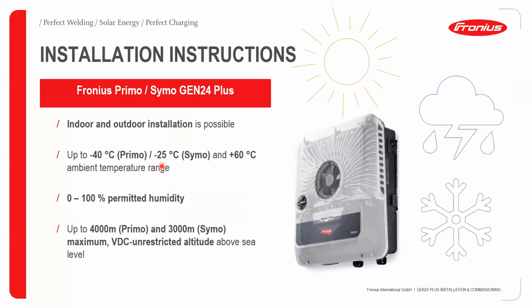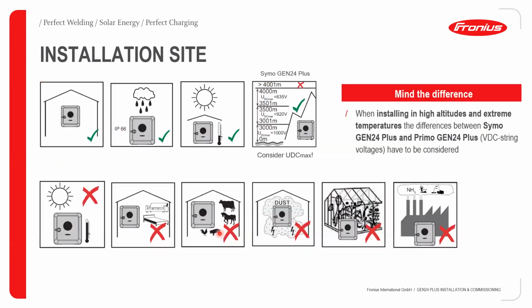Okay, so let's now have a brief look at some of the characteristics in terms of installation. It can be installed both indoors and outdoors. For ambient temperature figures, it ranges from -40 for the Primo, -25 for the Symo, up to 55 degrees Celsius, respectively. It has 0 to 100% permitted humidity. And in terms of altitude, the Primos can be installed up to an altitude of 4,000 meters above sea level. And then the Symos can be installed up to 3,000 meters above sea level. So to buttress on that, this is exactly what.